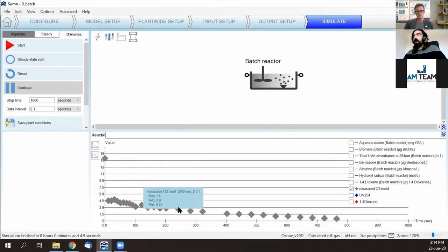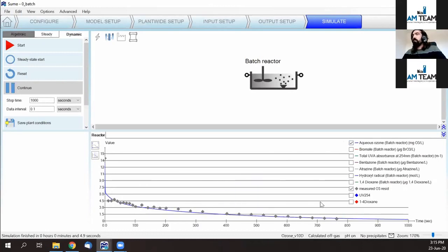And here below we are visualizing both measured and model data. Measured data will be these dots here, which we already included. These are real measurement data from a laboratory test, which we modeled and which we fit with our ozone profile, predicted ozone. Now, as you can see here, we pass nicely through the measured data, and we observe the typical profile that Wim just explained. So a first drastic drop at the beginning, which is the fast consumption of ozone, and then a slow decay in time.